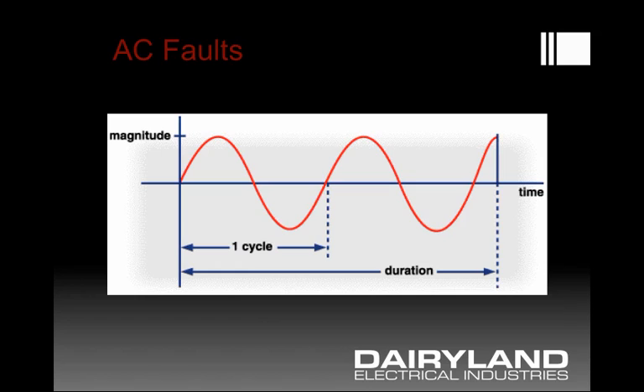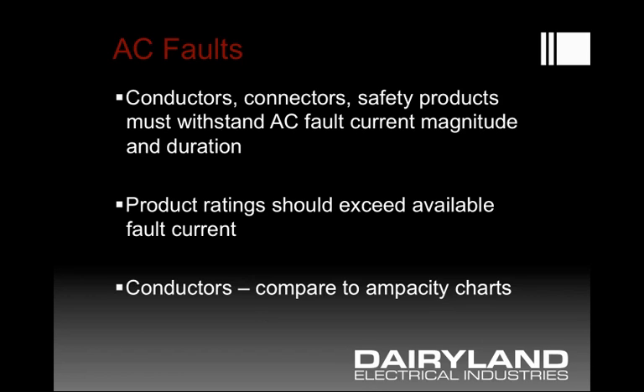Here you can see in this graph the periodic basis of this AC waveform, where one cycle is a complete positive and negative half cycle. The duration of a fault is defined as the length of that event, either in milliseconds or in cycles. AC faults result in heavy current flow, so all of the current conduction path must be able to withstand that AC fault current — including conductors, connectors, and bonds to pipelines. Products used for protection must have ratings that exceed the available fault current in order for them not to fail under those conditions.